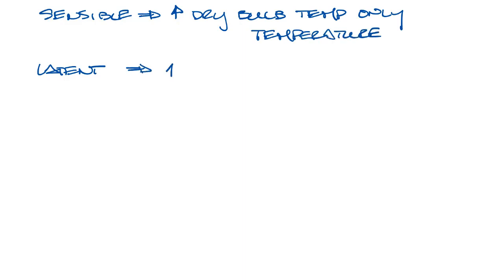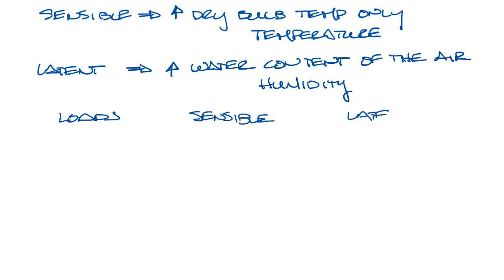The latent load raises the water content of the air. Think of this as humidity. So now let's look at loads and see whether they're sensible or latent. Lights, those are usually sensible loads. There's no latent component.